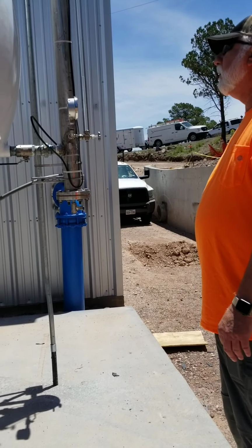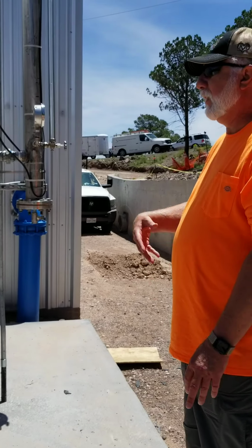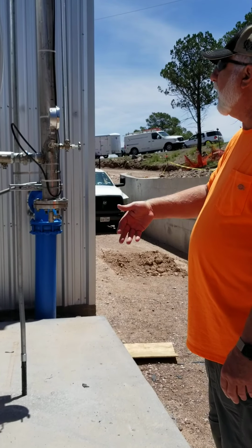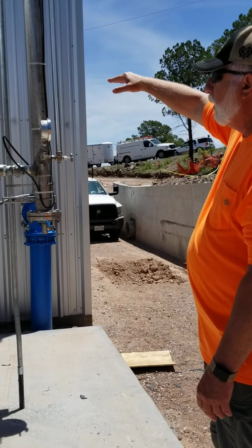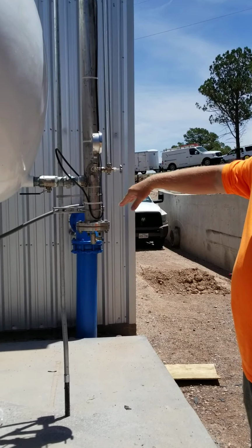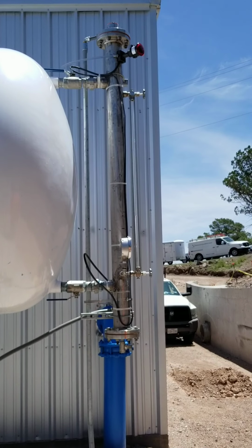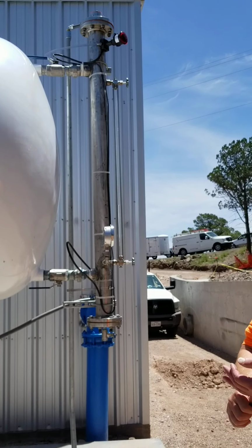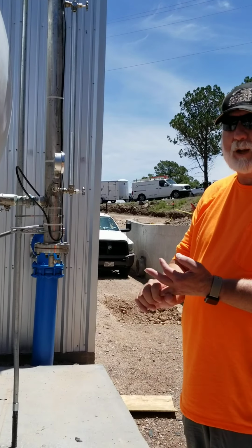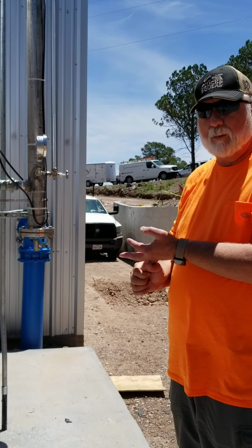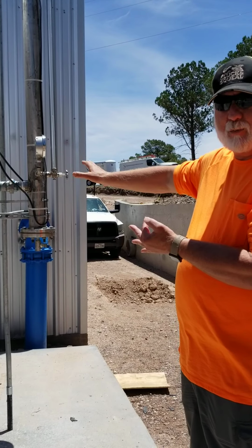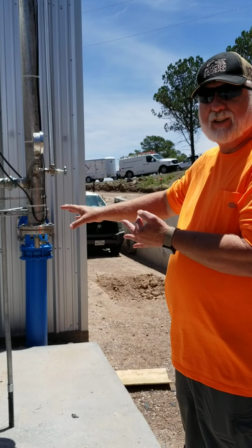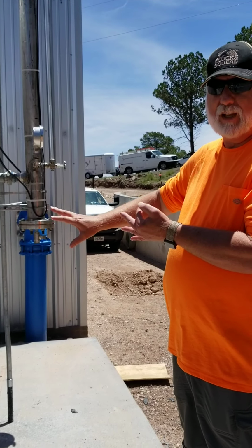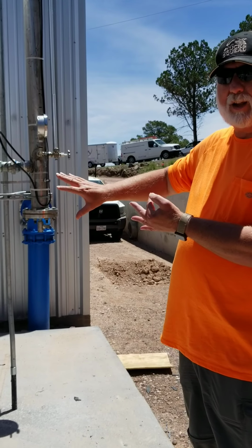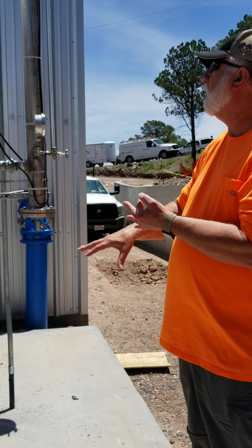Your tank, to get the most efficiency out of it, the water level is always going to be below the center of the tank because the air is being used. I like to refer to it as a battery. It stores the energy from the pumps. The hydromatic tank and the air compressors, none of that adds any pressure to your system. It is there solely to maintain the pressure that the pumps create.